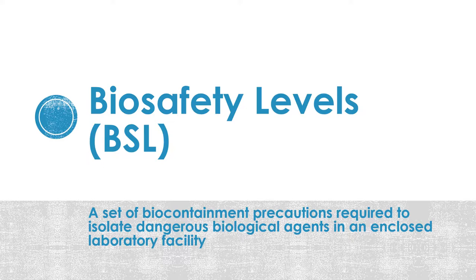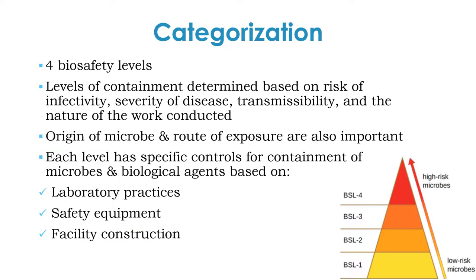Biosafety levels are sometimes referred to as containment levels. They are a set of biocontainment precautions required to isolate dangerous biological agents in an enclosed laboratory facility. There are four biosafety levels where the numbers represent increasing virulence of the microbes being handled, so biosafety level 1 deals with low-risk microbes and biosafety level 4 handles microbes with the highest risk. The levels of containment are determined based on the risk of infectivity, severity of disease, transmissibility, the nature of the work conducted, origin of the microbe and route of exposure. Each level has specific controls for containment based on laboratory practices, safety equipment and facility construction.